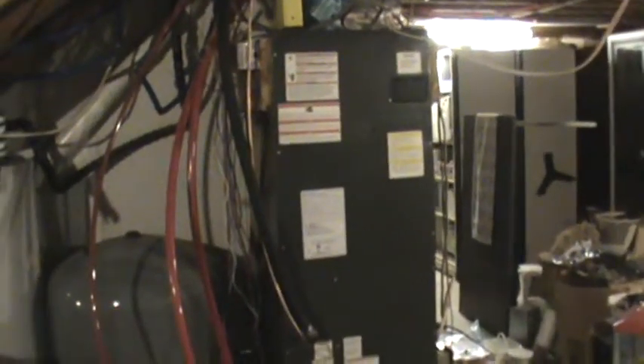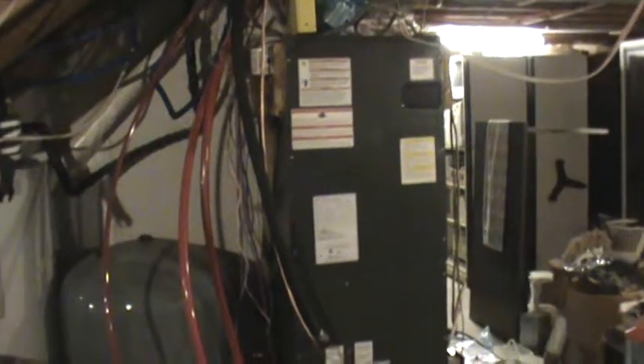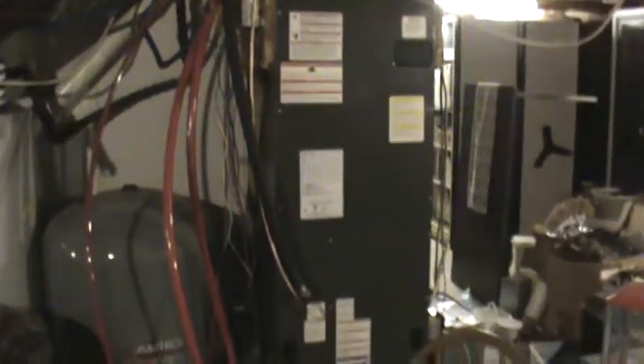And so as it expands, its temperature drops, some of it boils off, and then the A coil inside acts as an evaporator, takes the rest of the liquid, boils it off, so that the refrigerant is accepting heat from the air that's flowing through this. By the way, the airflow through this thing is from the bottom. You can kind of see down there, that's the bottom of it. It's off the floor a little bit.